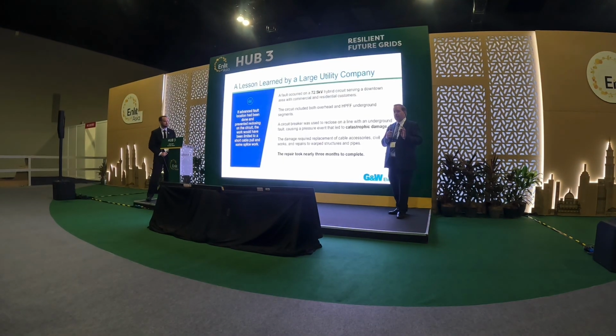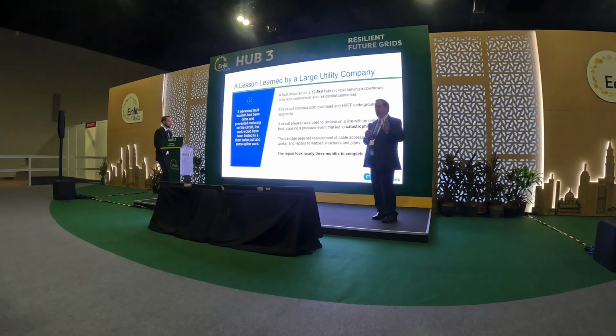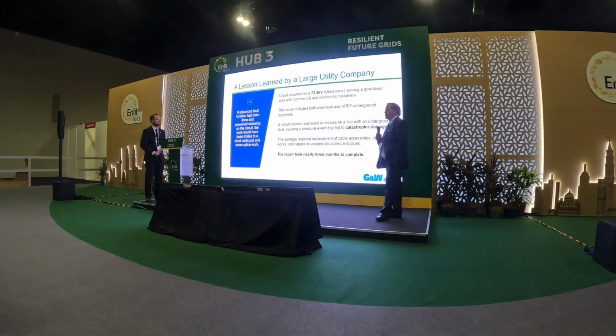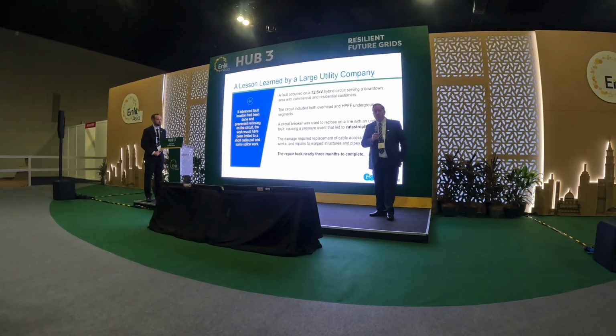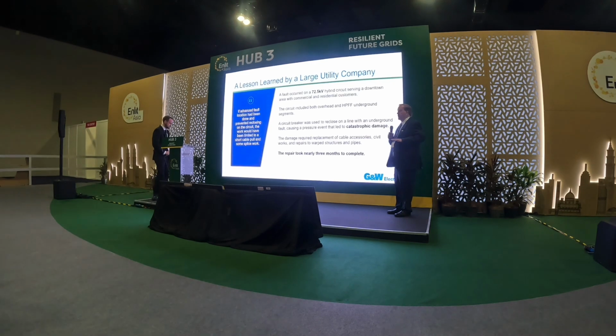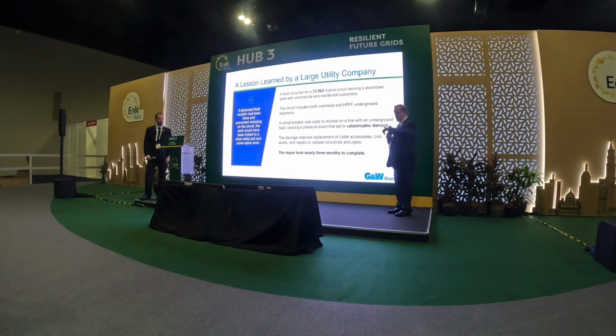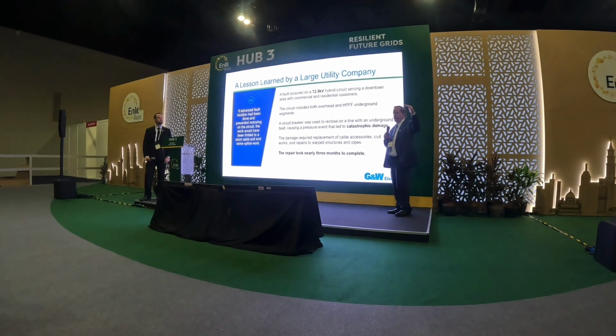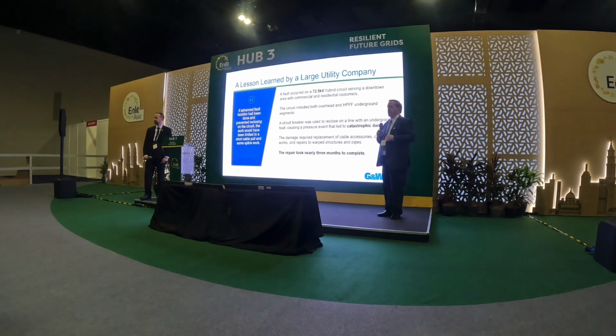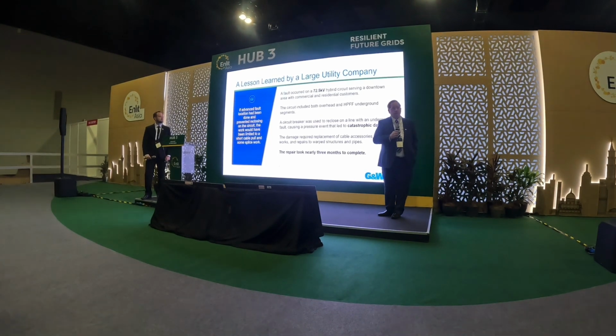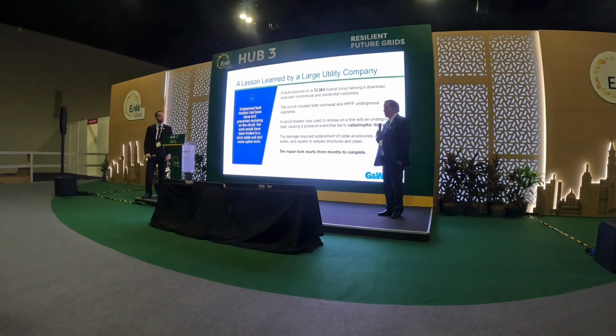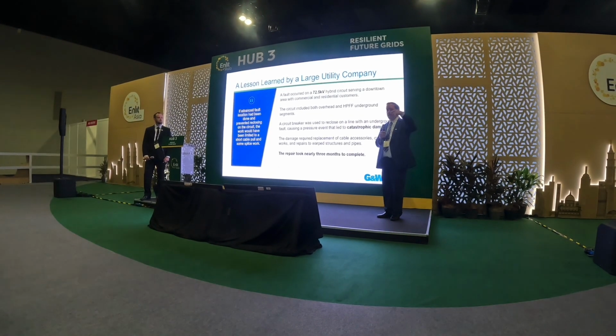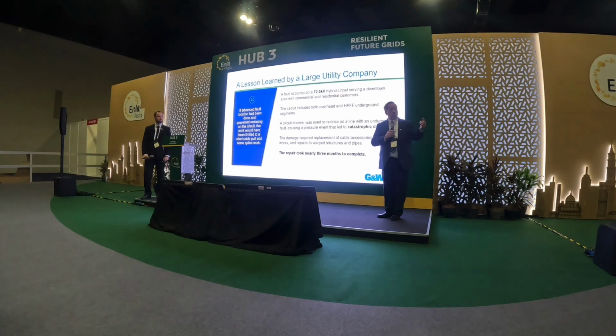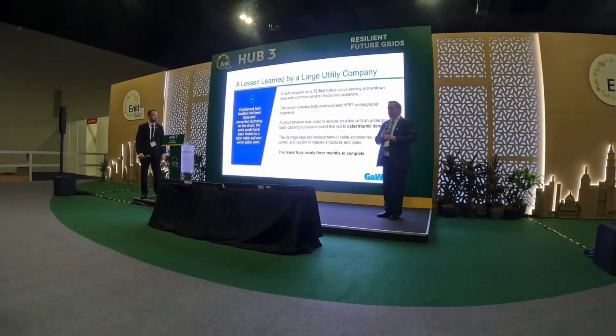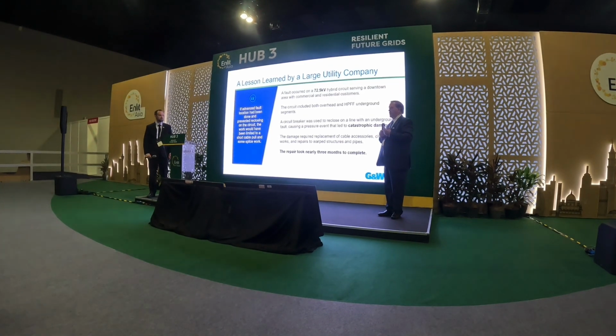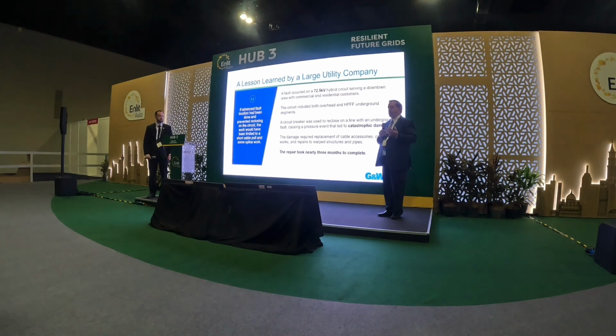So let me share really quickly an actual cautionary tale. I cannot tell you where this occurred, but there was a 72 kV line, and this particular line had high pressure fluid filled underground cable in the underground portion, but it had an overhead line going into that feed, and they had a fault. They did not properly determine where the fault was located, and they reclosed back in on that permanent fault. And the pictures of this are extremely moving, let's say.